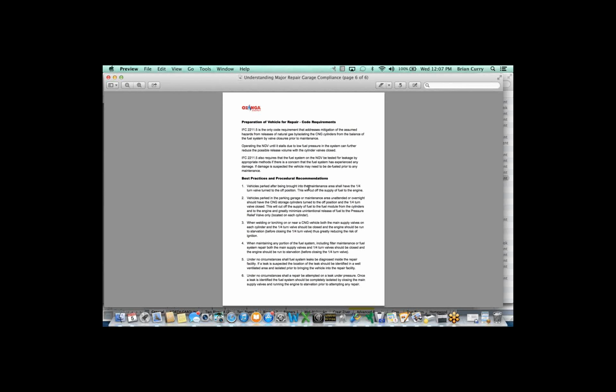And lastly, number 6, again, a no-brainer. I have horror stories I can share with you at another time on this one. Under no circumstances should a repair be attempted on a leak under pressure. In other words, if you've got a line under pressure from the cylinder all the way up to the engine and you've got a small leak, I can't tell you how many times I've seen mechanics take a channel lock or a crescent wrench out of their back pocket and go to tighten that fitting. It's probably one of the stupidest things you can do. I've seen lines fail because they weren't crimped properly. So again, identify the leak first, isolate it, and then repair the leak with no fuel in the system whatsoever.